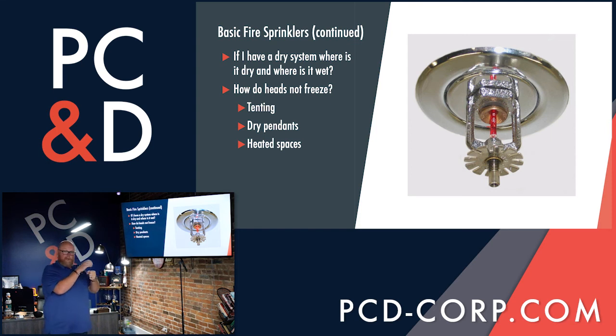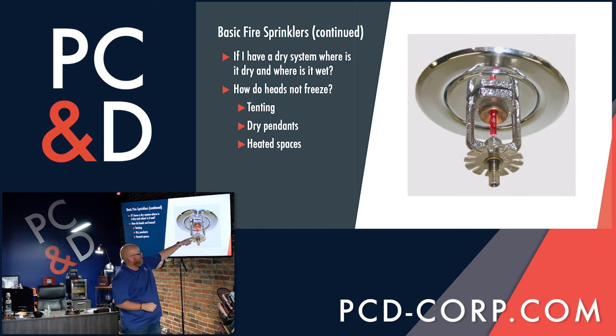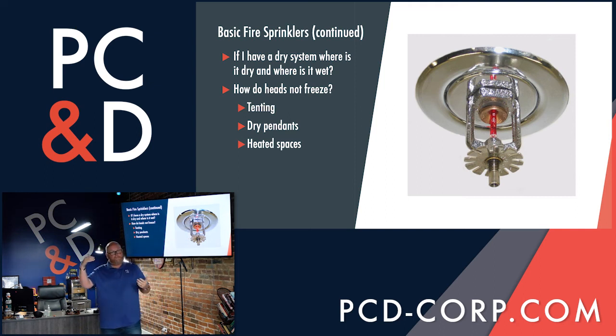As that chemical expands, it will literally bust the little glass tube that is holding this piece back. When this reaches a certain temperature that it's engineered and designed to do, it expands, the small glass tube busts, and this spring-loaded head here will drop. As soon as it drops, right behind it is whatever system you have. As we mentioned earlier, if it's a wet system, right behind it's water, water's coming immediately. If it's a dry system, that head drops, it disperses the air, and then here comes the water.